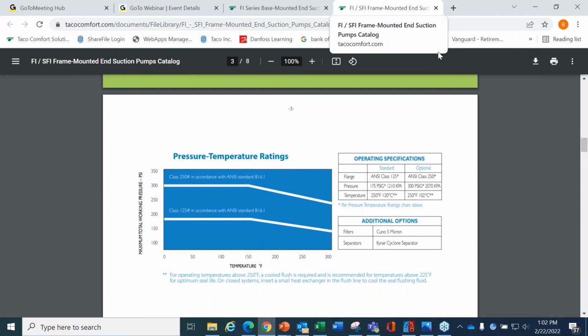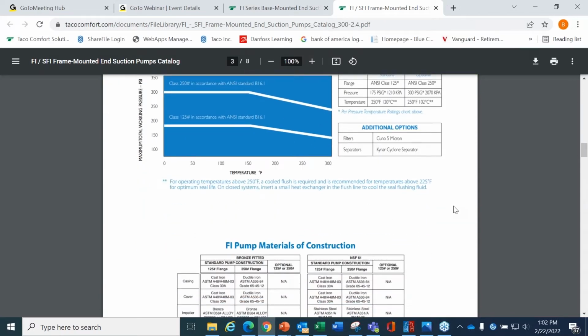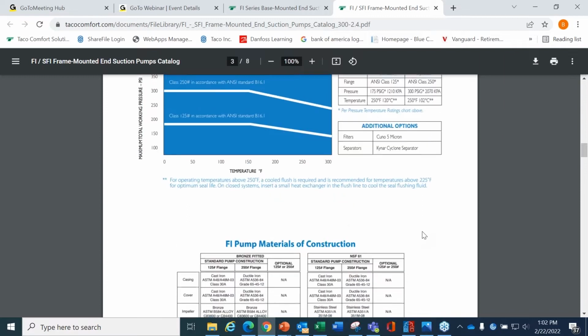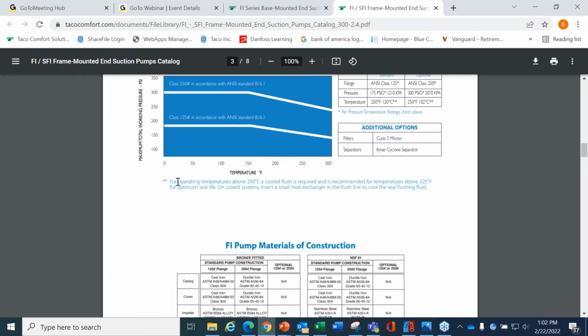Here's what I would recommend: that you contact your local rep. And then we can get together with the rep and look at your temperature requirements and make a recommendation. Generally speaking, the temperature requirements will be limited by the seal choices. See right here, Rich, in our manual it says above 250 a cooled flush is required, and it's recommended for temperatures above 225.